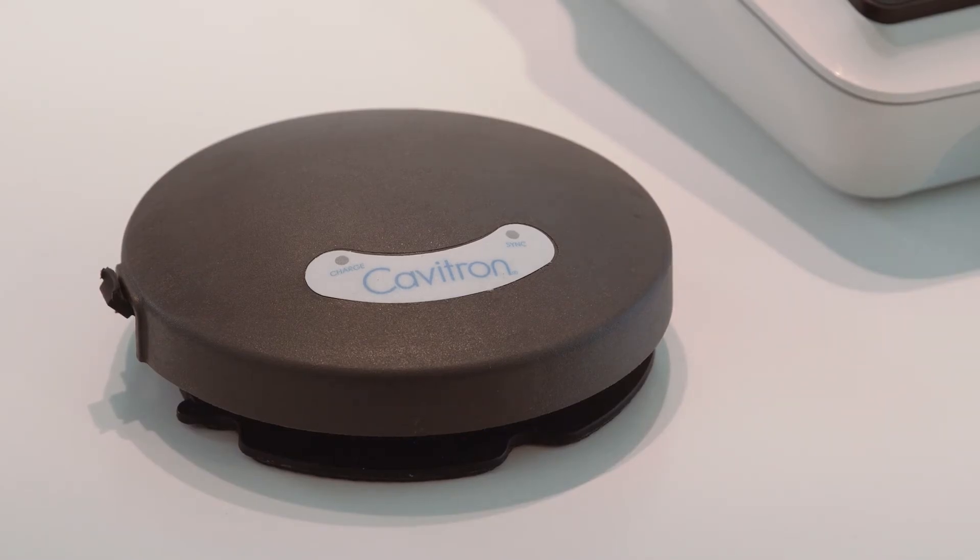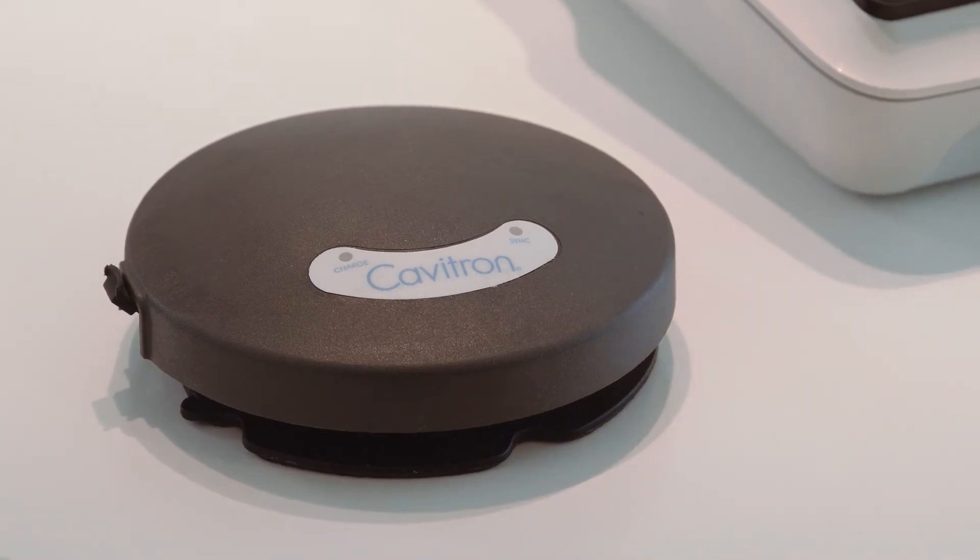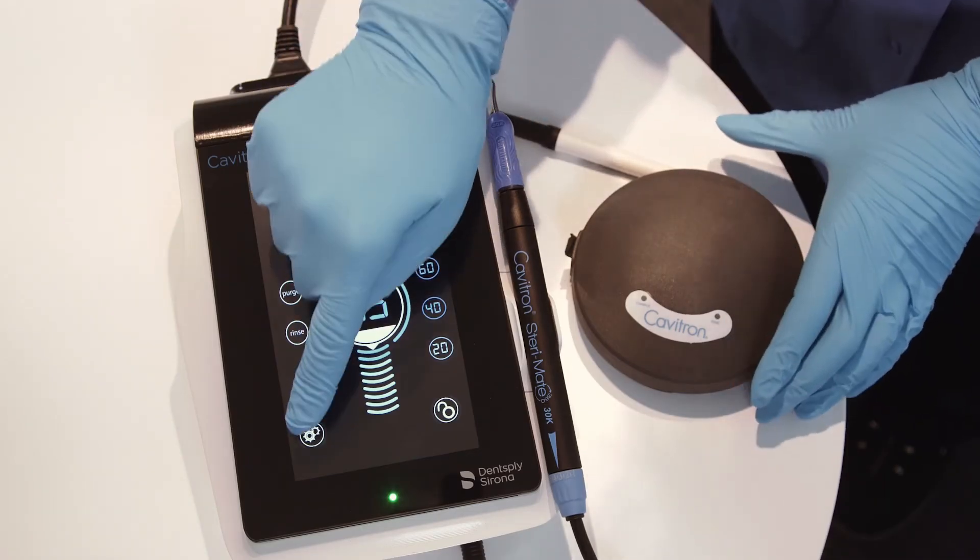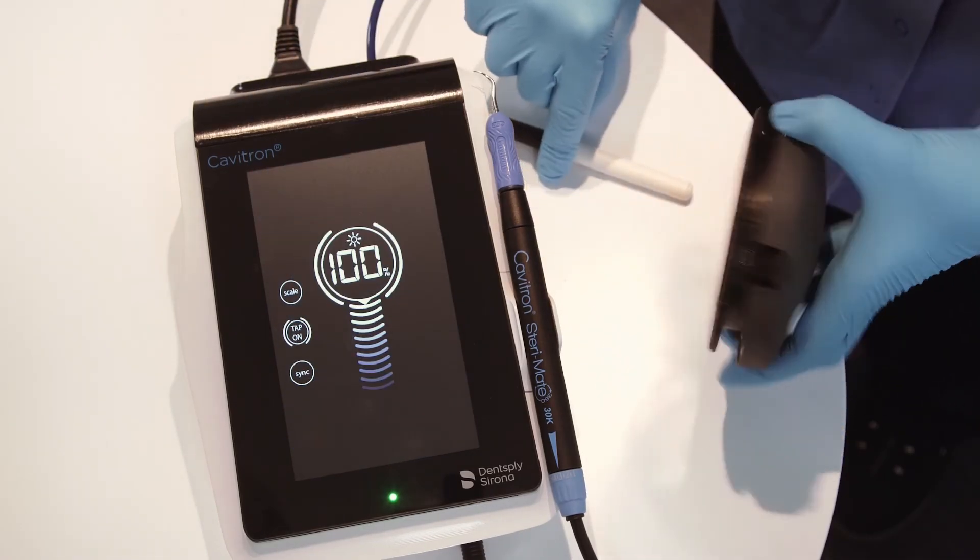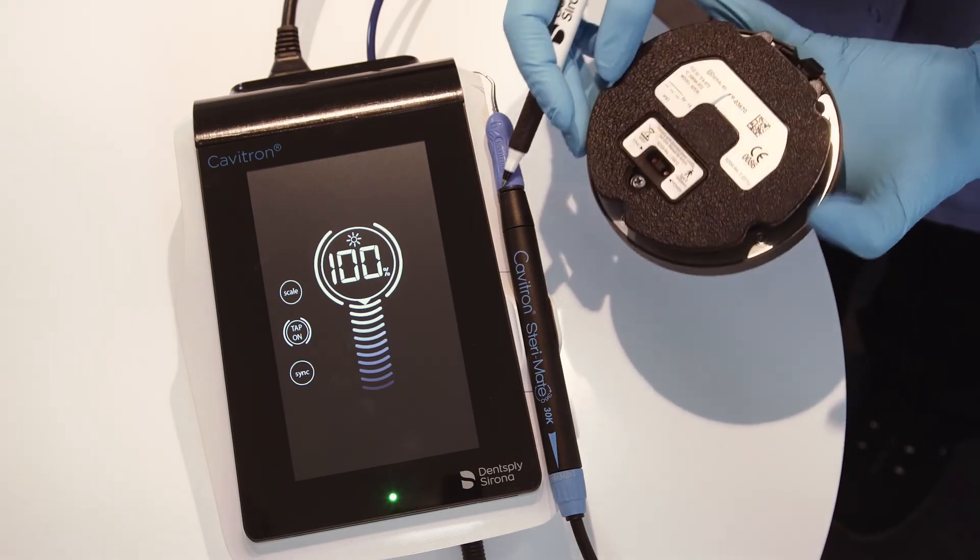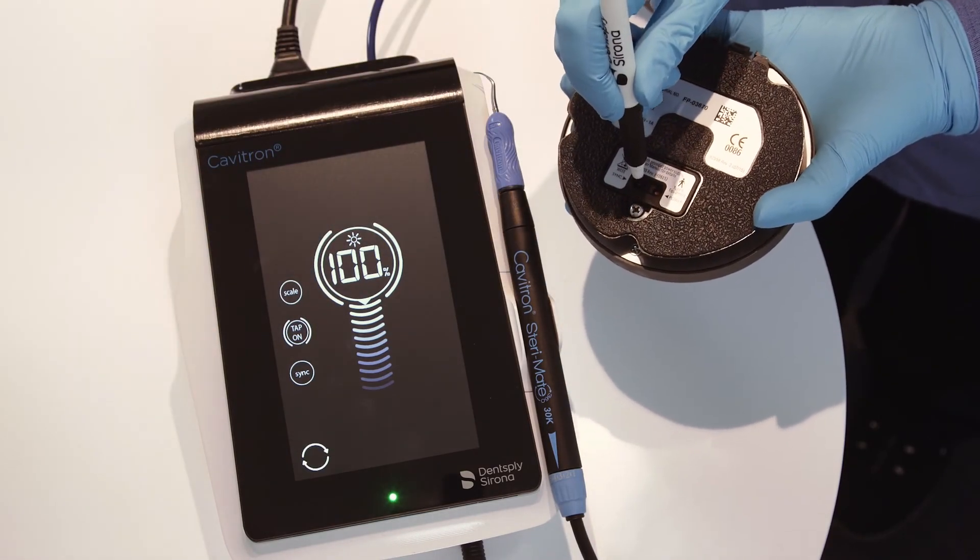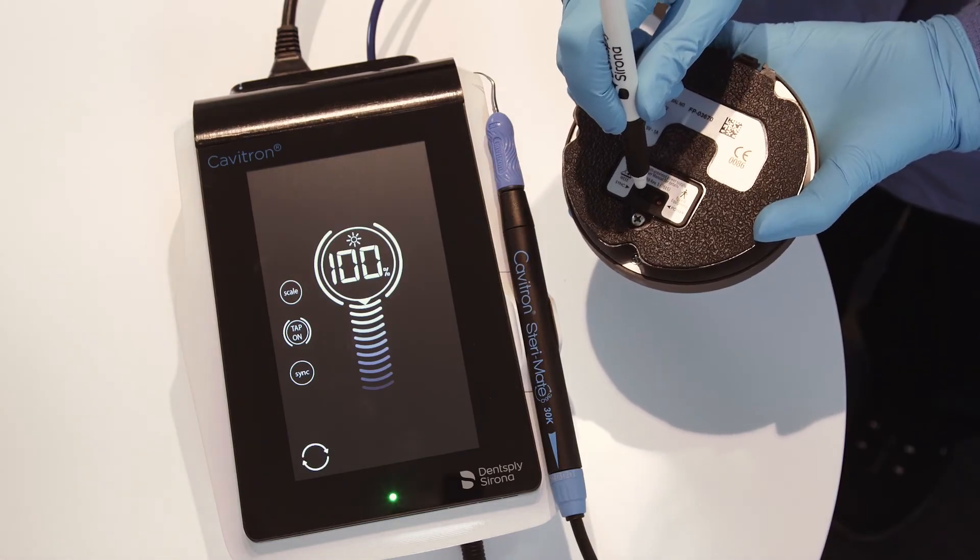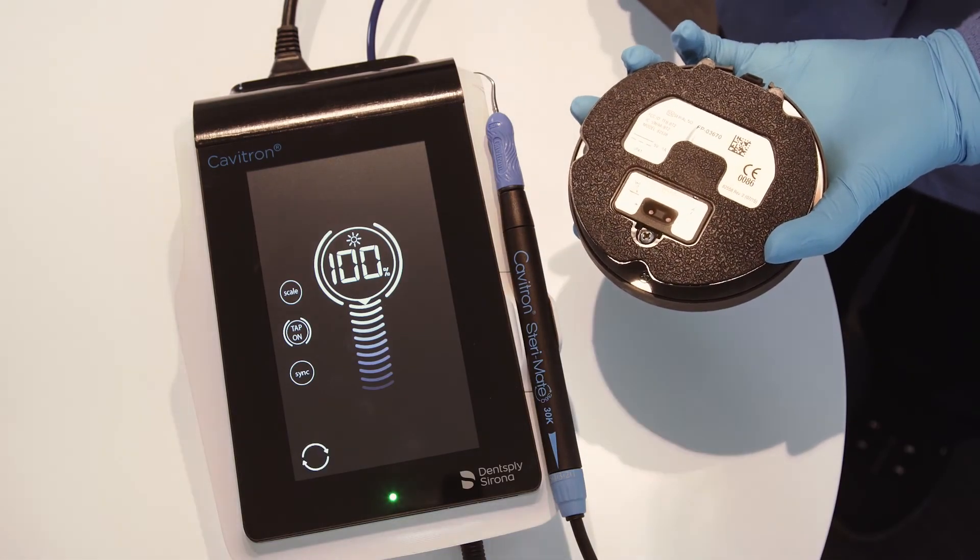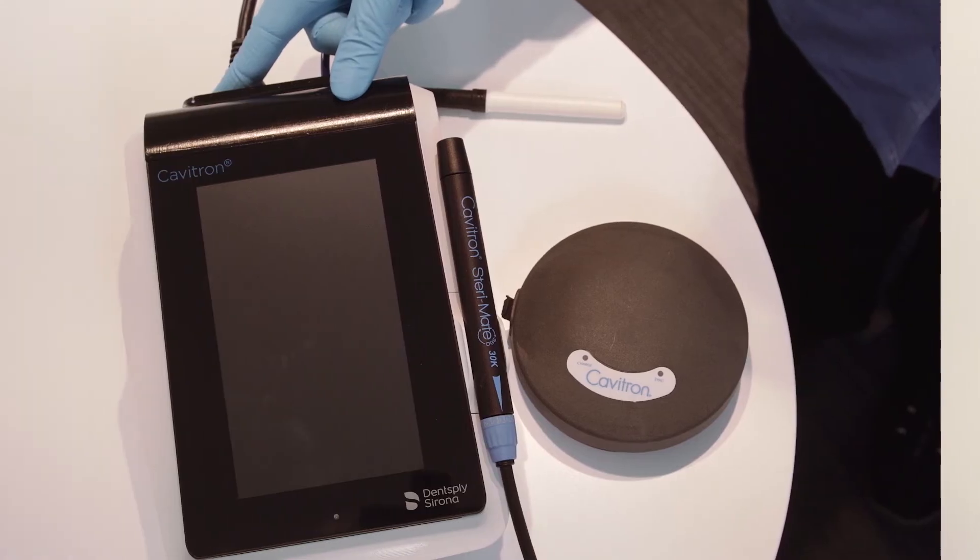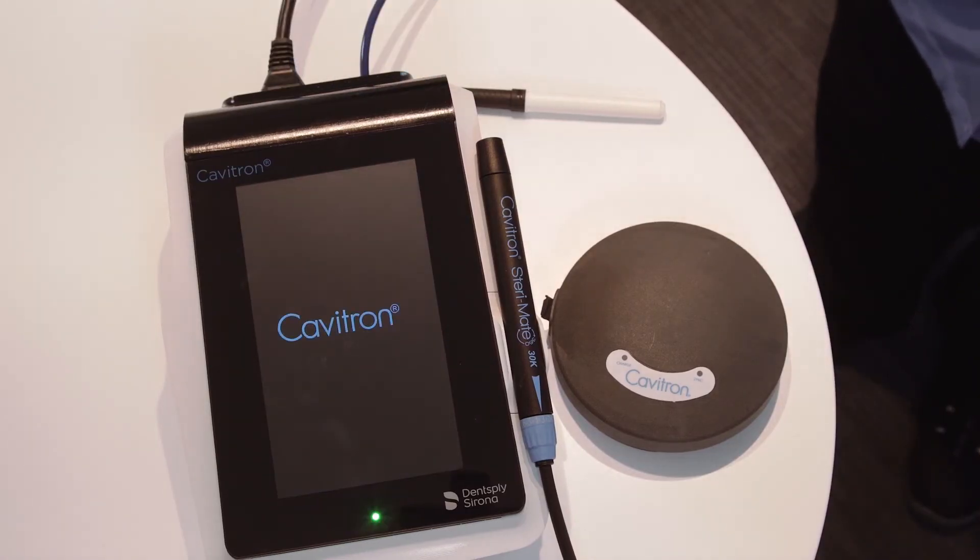The tap-on wireless rechargeable foot pedal supplied with your system has been factory synchronized with the base unit. Should a replacement foot pedal be necessary, synchronization will be required prior to system operation. Users should maintain a distance of no more than 10 feet between the base unit and tap-on foot pedal during the synchronization process. To synchronize your foot pedal, begin by turning on the main power switch located at the rear of the system to the on position. The main screen will appear. This is also referred to as the scaling menu screen.